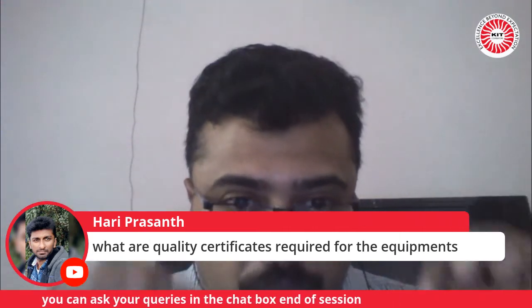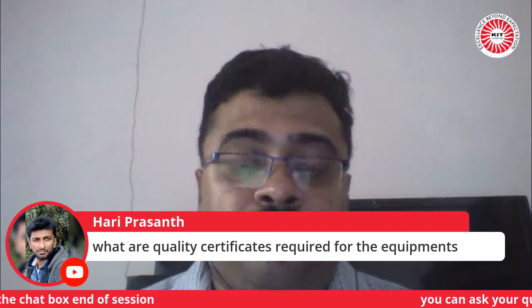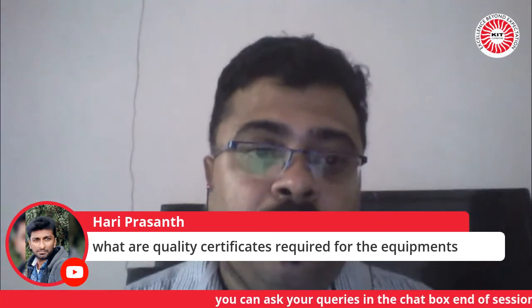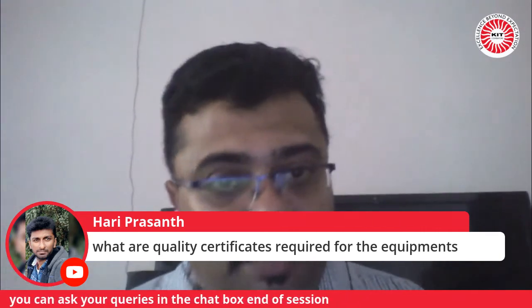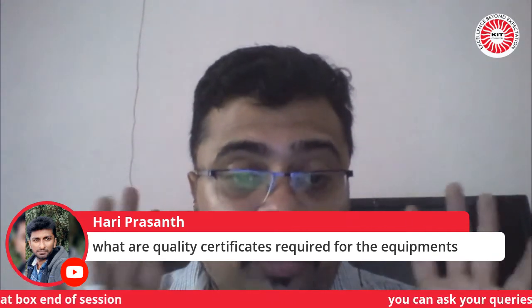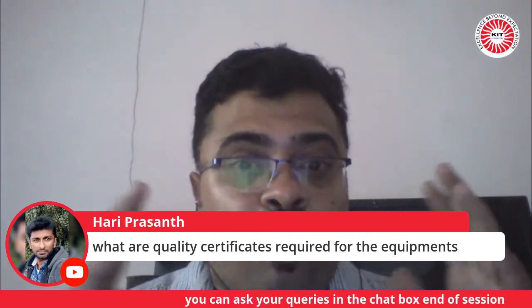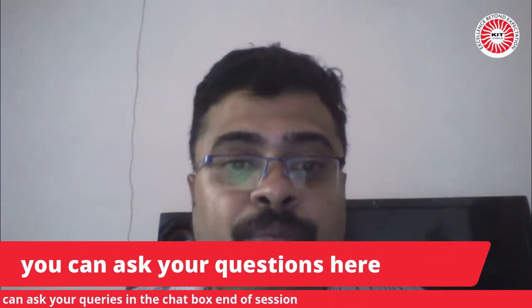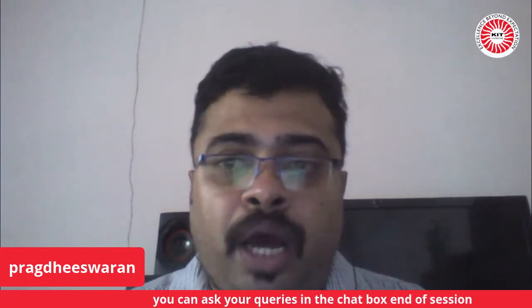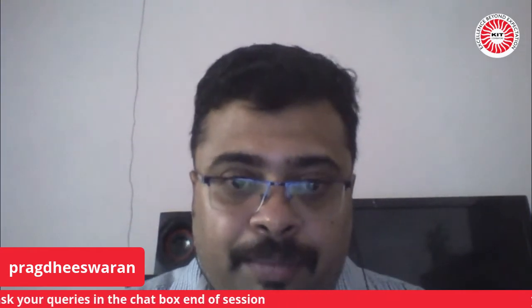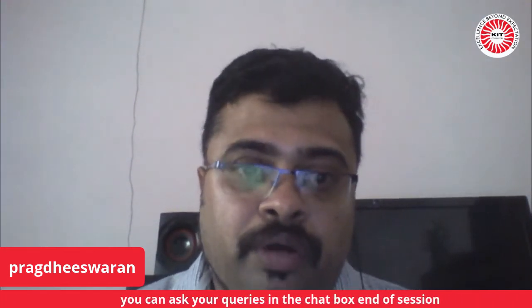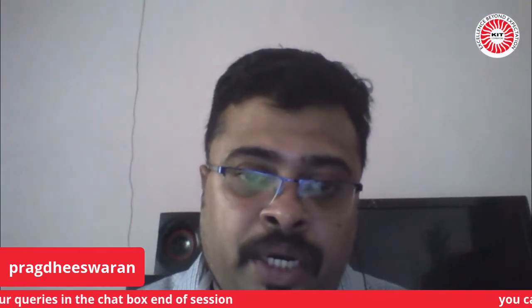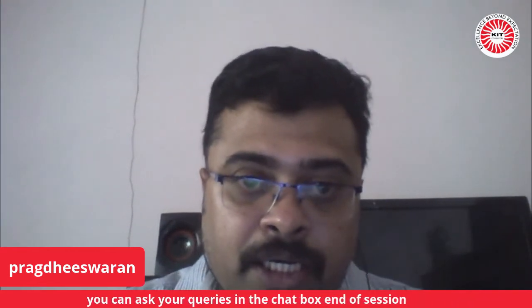That again tests my equipment against collateral and particular standards. For that, I have to take it to a big lab, to first pass the collateral standards and particular standards on a sample of one or two equipments. But I cannot qualify every single equipment coming out of my production floor. For production floor output, every equipment I put across a calibrator to take a basic certification of performance, and connect it to a Fluke electrical safety tester for certification of insulation and so on.